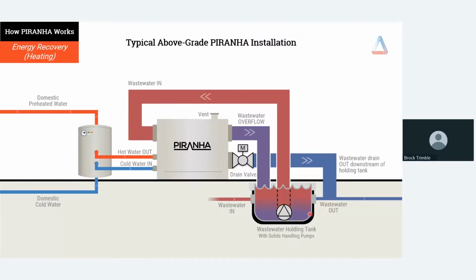And ultimately, we have down here what we call a drain valve. We open that up. It's just an automated ball valve, and we get rid of all of the used liquid and solids that we've moved using that pump directly downstream and out to the city sewer. So we're really only temporarily catching that wastewater in order to gain access to that energy before sending it on its way, as would be normal with any building application, down to your sewer, down to your treatment center, to be treated and discharged out to environment as it normally would.